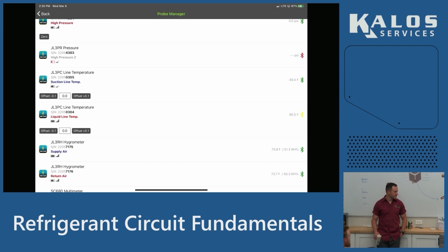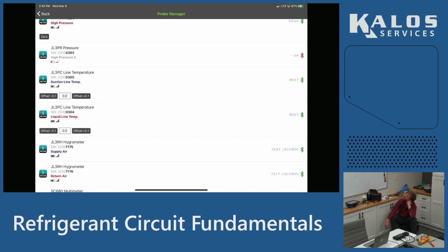All right, that brings us to number 3. What is the third most common reason we come up and find low suction pressure? Now, Adam has got us both of the first two. Anybody else want to guess the third? You have like restrictions in the metering device.